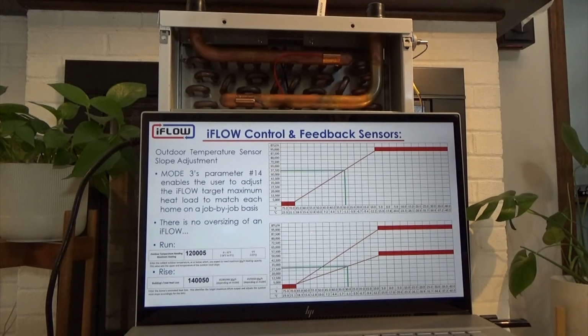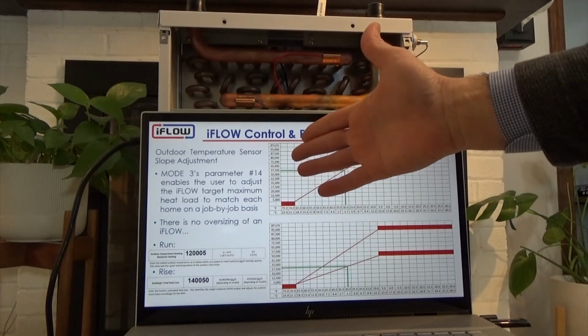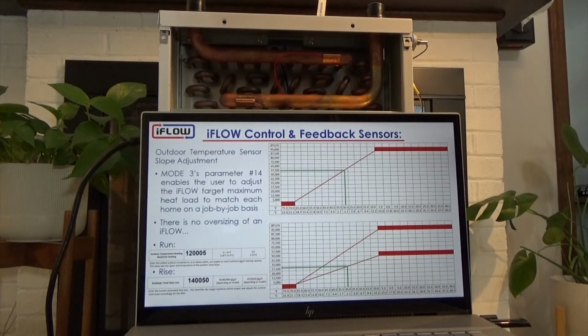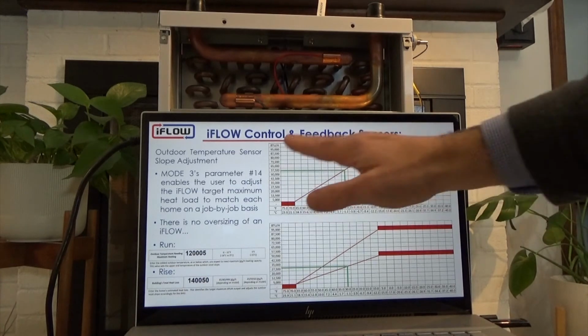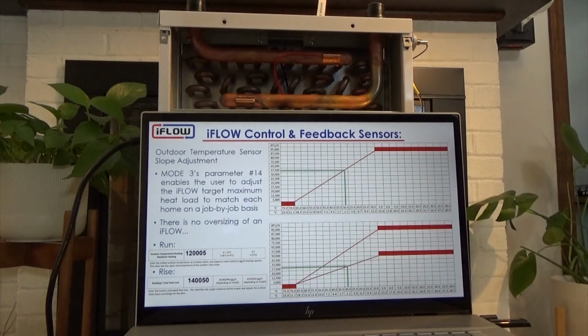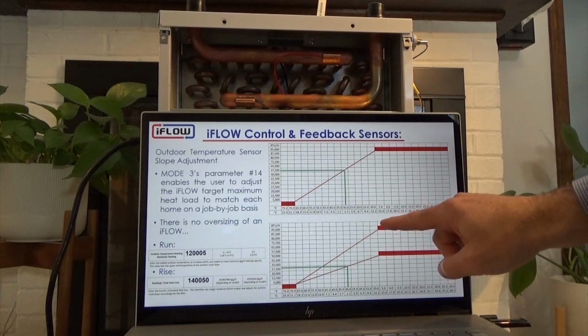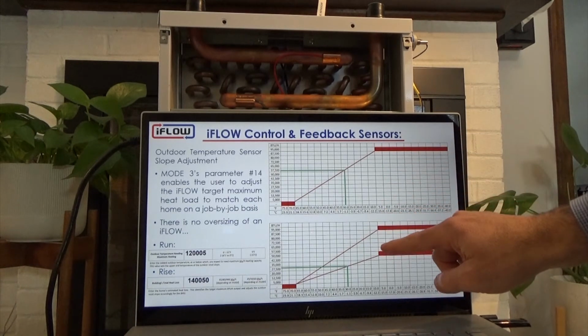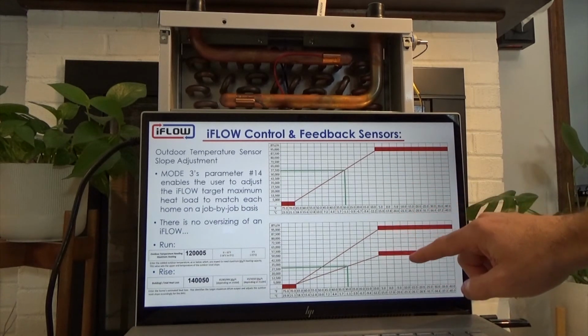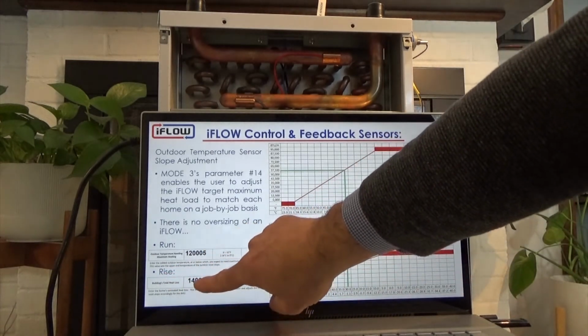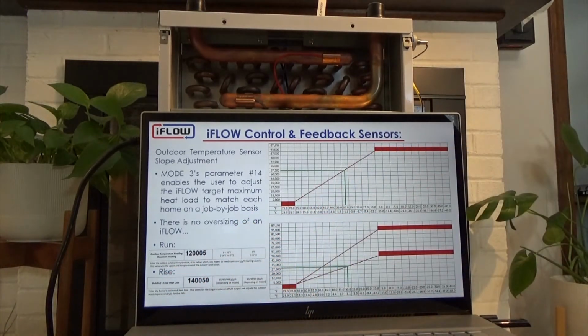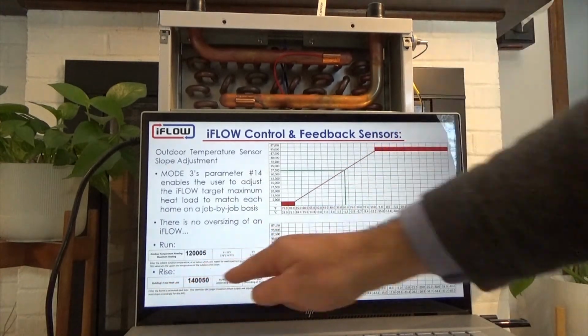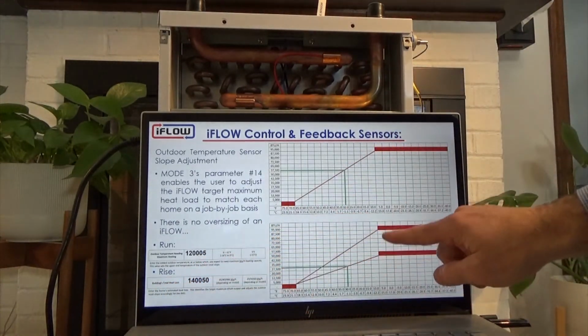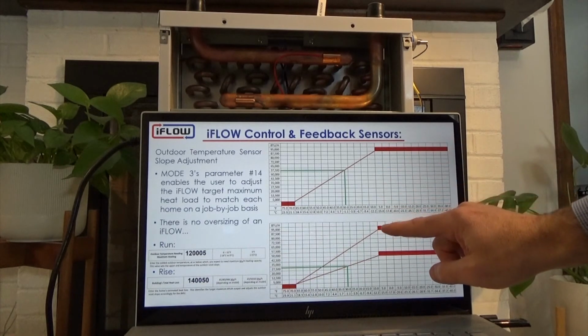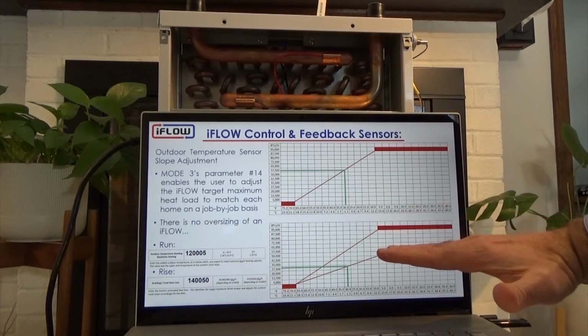We can then adjust the position of that curve. So for example, let's say you're using the 18,000 series unit that's capable of 95,000 BTUs, but perhaps you only need 50,000 BTUs. Well, we can adjust that maximum down to 50,000 BTUs, and we do that using our parameter 14 in the heating section. Right, we have the building's total heat loss. So at that parameter 14, we would adjust from 95 down to 50.